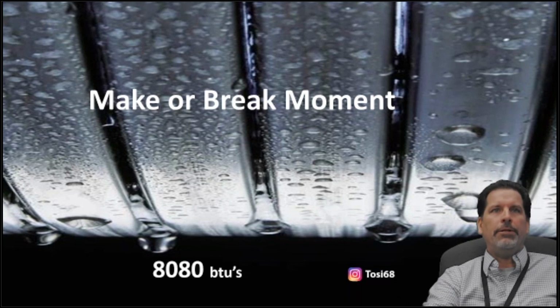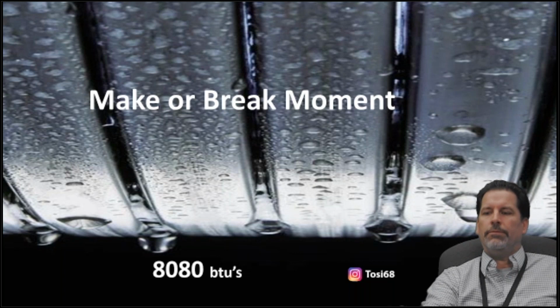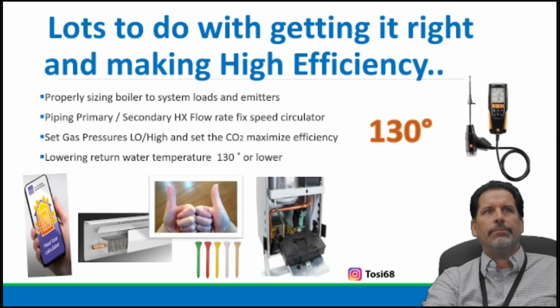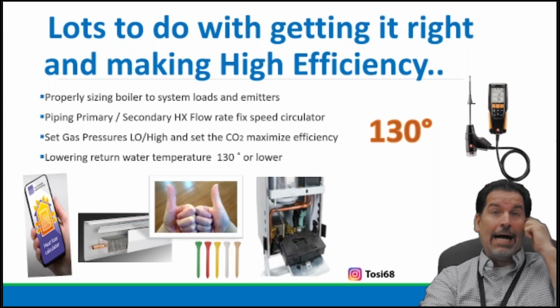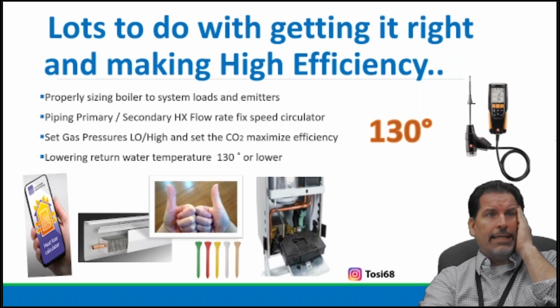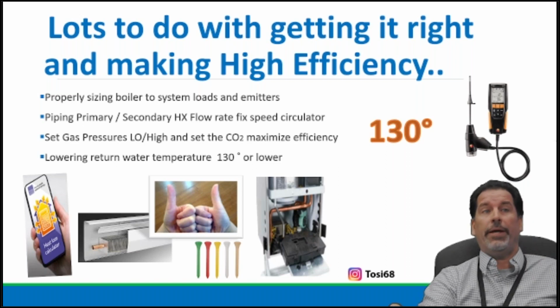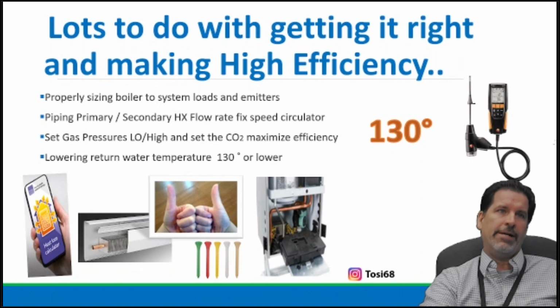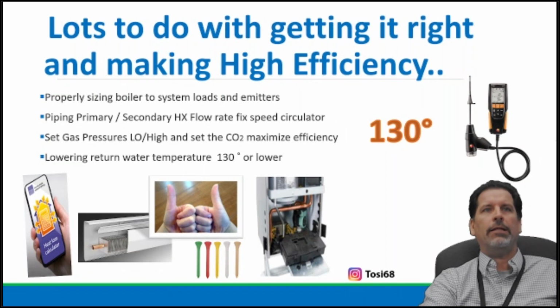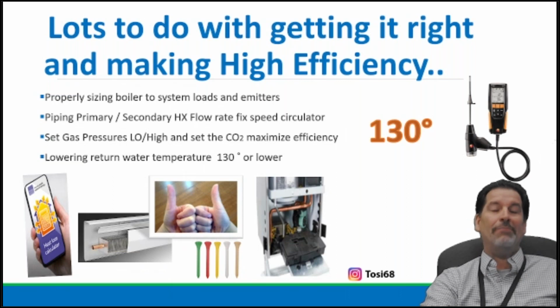Reclaiming close to 8,100 BTUs, every gallon of condensate you can pull back out of a vapor to a liquid. So a lot to do with getting it right, and making high efficiency. Again, sizing the load and emitters to the space, right? We do a heat loss. Primary, secondary, heat exchanger flow rate, fixed speed circulators, understanding the equipment of choice, what the manufacturer specifies, setting of gas pressures, high and low, calculating or calibrating with a combustion analyzer. Again, maximizing, collapsing the CO2, lowering water temperature, 130 or lower, right? That's key. 130 is the threshold to start. I'm happy if you do that.